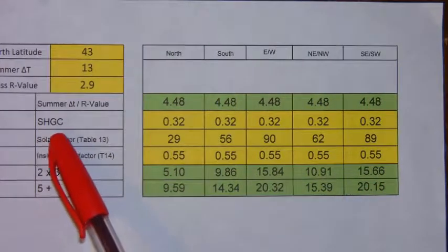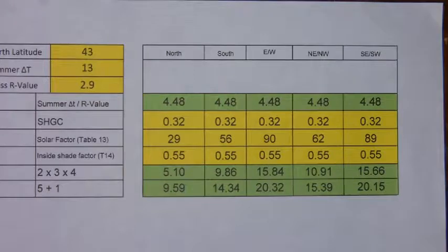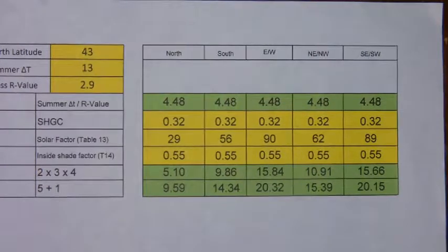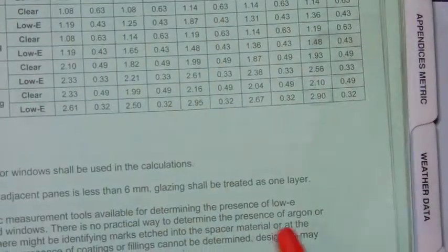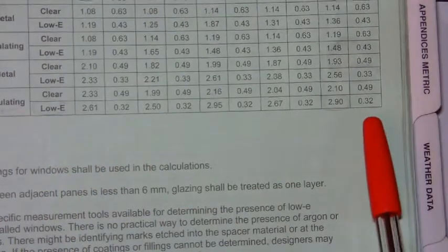The solar heat gain coefficient comes from your HRAI manual, and depending on the type of glass you have, you would have a solar heat gain factor. In our example, we had an operable wood vinyl with insulating low E, and we used a factor of 0.32.